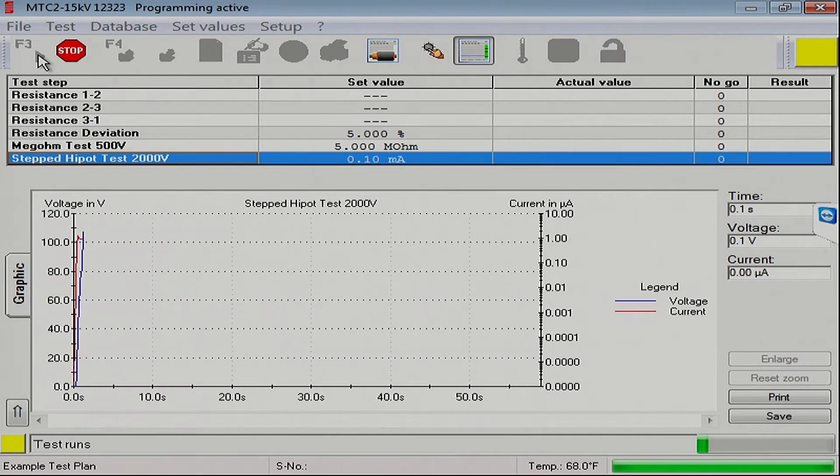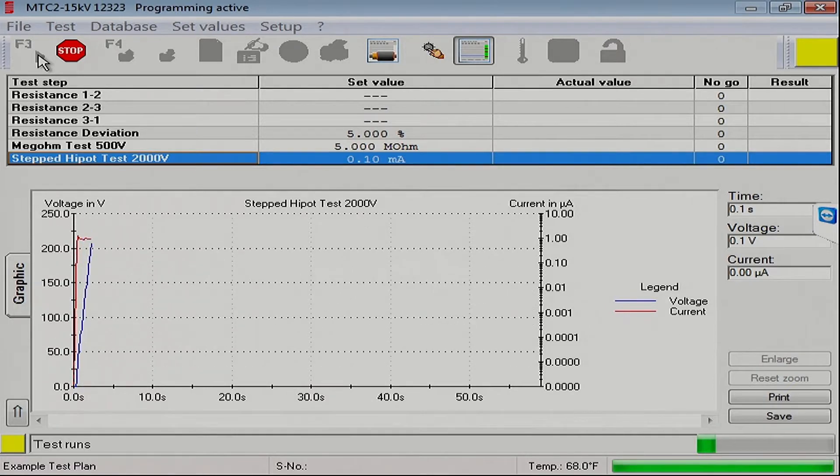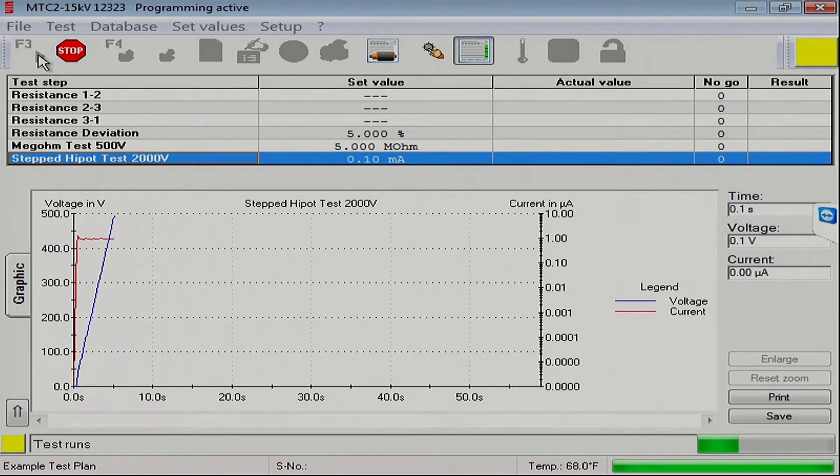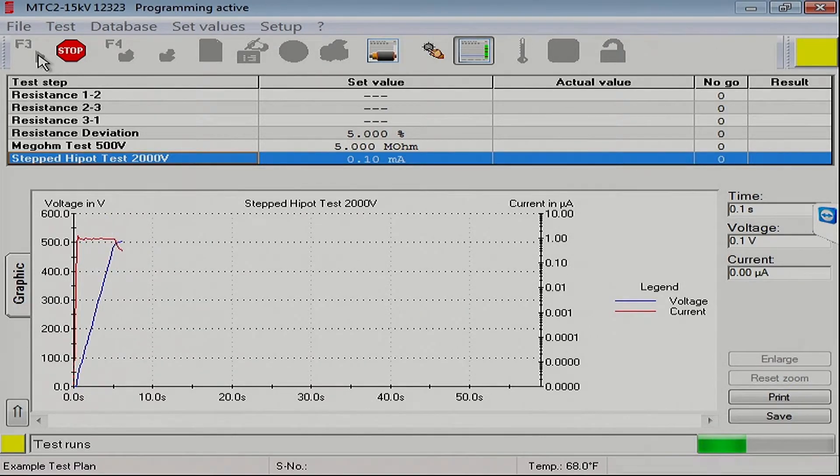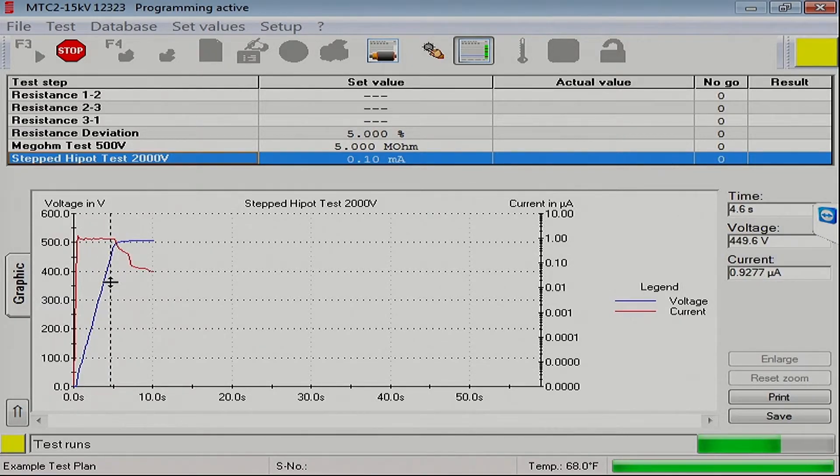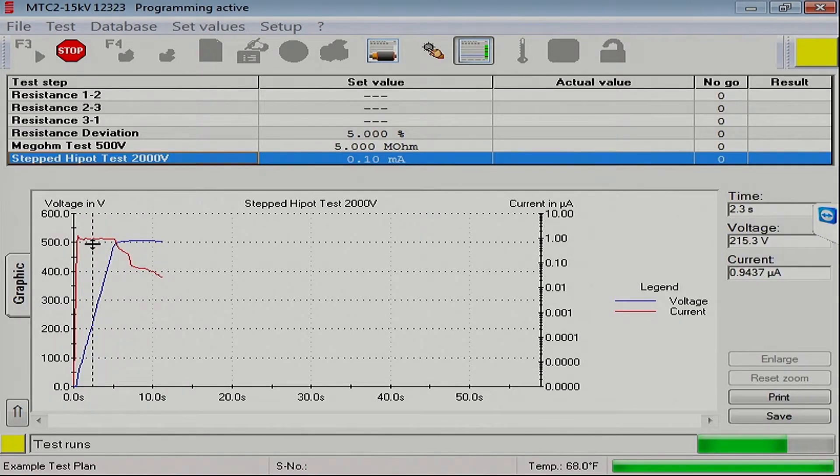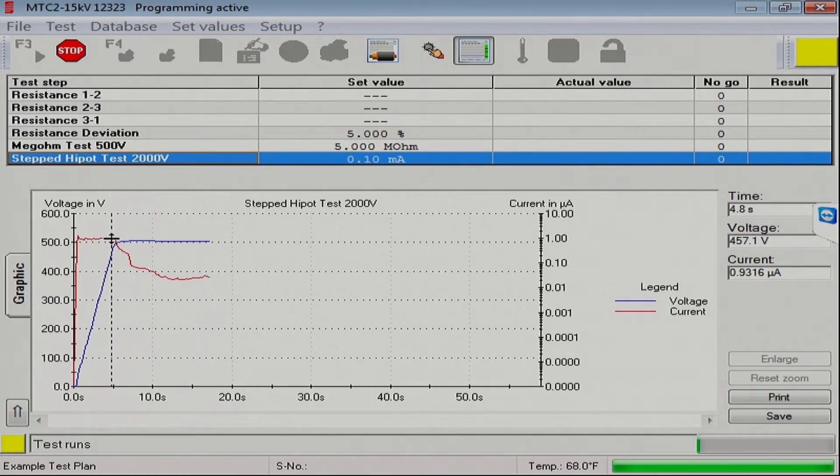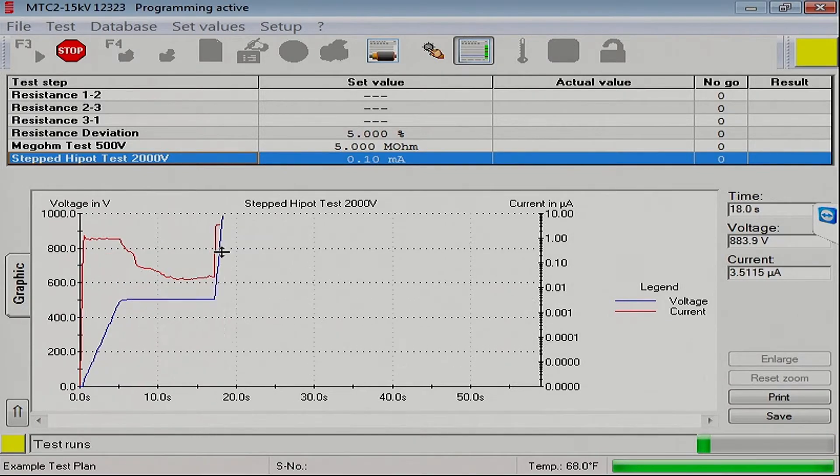So there we go. Current is the red trace. Voltage is the blue trace. You can see in the very first part here we ramped up. Current was a little high as we were charging the ground wall capacitance of the stator.